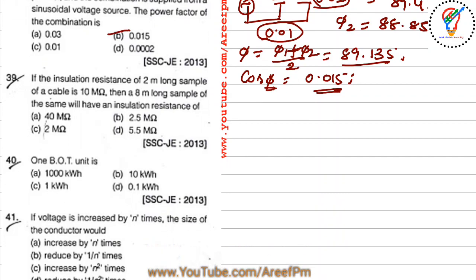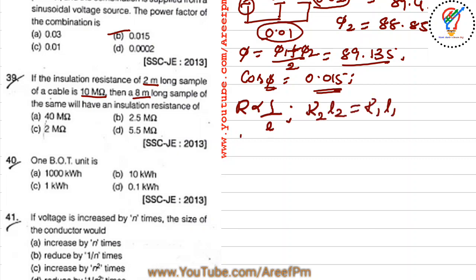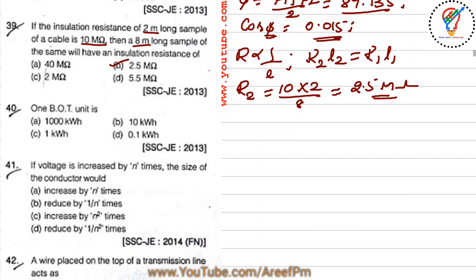Next question: if the insulation resistance of a 2-meter-long sample of cable is 10 mega ohms, what will an 8-meter-long sample of the same cable have? Insulation resistance is inversely proportional to length. So R2 × L2 = R1 × L1, giving R2 = (10 MΩ × 2) / 8 = 2.5 mega ohms. Option B is correct.